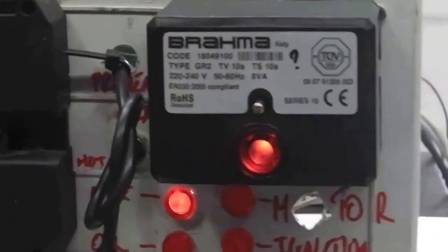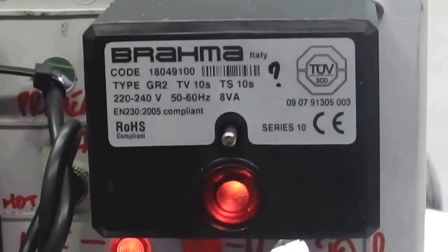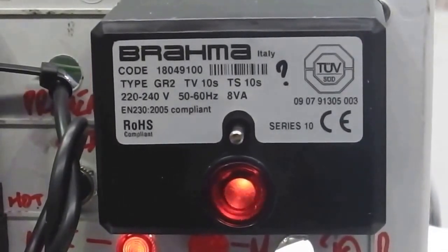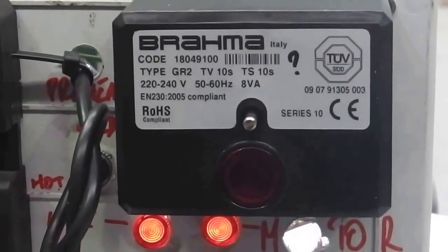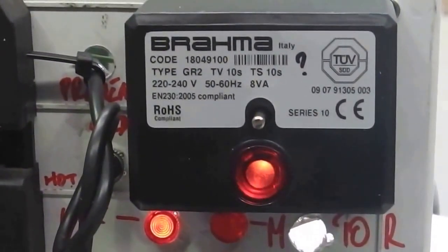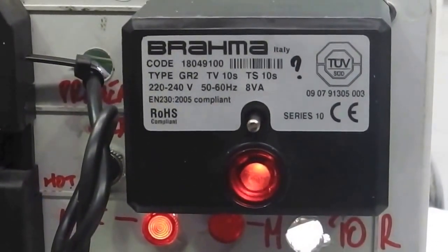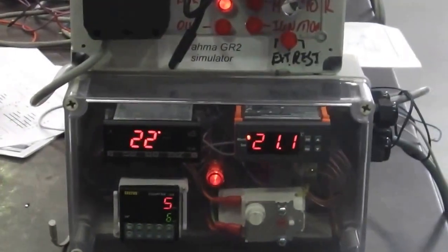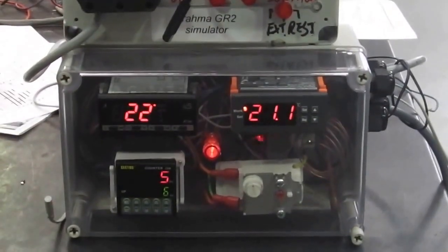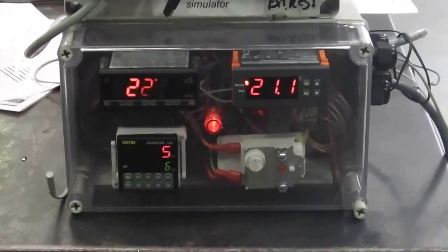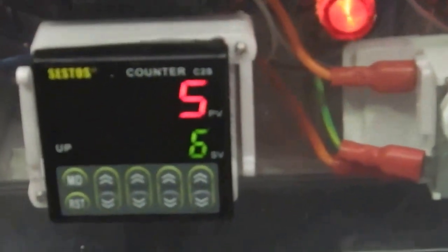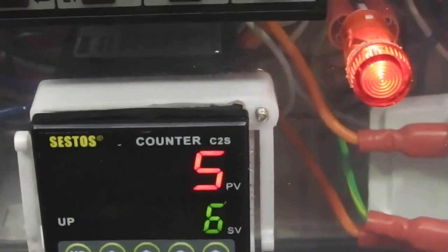Right there you can see the Brahma controller, and the flame failure button we can see is on, and it's been provided an automatic restart by our control box down the bottom. Okay, what we got is the Sestos timer, bottom left hand corner, the red display set to number 5, which is the PV or present value. And the set value is the green below that, of 6.